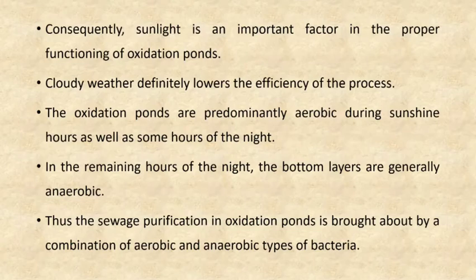Consequently, sunlight is an important factor in the proper functioning of oxidation ponds. Cloudy weather definitely lowers the efficiency of the process. These oxidation ponds are predominantly aerobic during sunshine hours, as well as some hours at night. And in the remaining hours of the night, the bottom layers are generally anaerobic. So here is a combination of aerobic and anaerobic types of bacteria.